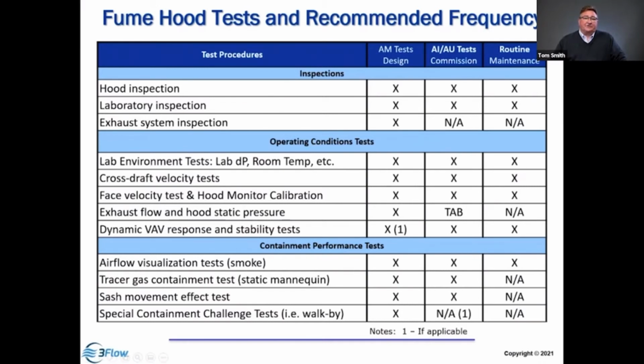The as-installed test is performed after the hood has been installed, the proper testing, adjusting, and balancing has been completed, and all the parts and pieces have been commissioned. Then we apply the test to set the baseline or the benchmark for the future operational tests.